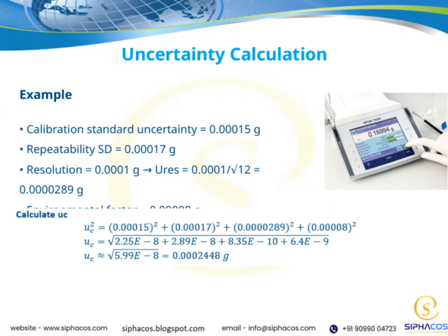When we look at the calibration standard uncertainty, we're talking about 0.00015 grams. This value reflects how precise our calibration process is and helps us understand the potential variation in our measurements. Next, we have the repeatability standard deviation, which is 0.00017 grams. This tells us about the consistency of our measurements when we repeat the same process under the same conditions. Moving on to resolution, our instrument can detect changes as small as 0.0001 grams. To incorporate this into our uncertainty, we divide that by the square root of 12, which gives us approximately 0.0000289 grams. This step accounts for the variability associated with the resolution of the instrument.